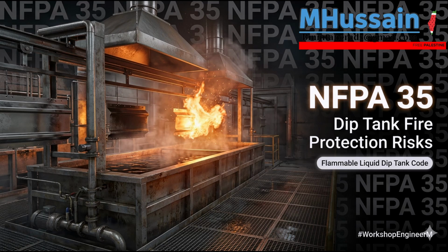And when we talk about the ultimate failsafe, we have to look at the fire protection systems. Section 11 mandates heavy sprinkler systems governed by NFPA 13 and highly specialized foam suppression systems dictated by NFPA 11 and 16. But there is a vital, often overlooked layout consideration here for the civil and plumbing engineers. Oh, the drainage. Yes. If a fire breaks out and you have massive deluge sprinkler systems suddenly dumping thousands of gallons of water per minute, combined with a foam system pumping out thousands of gallons of thick foam, where does all that liquid physically go?